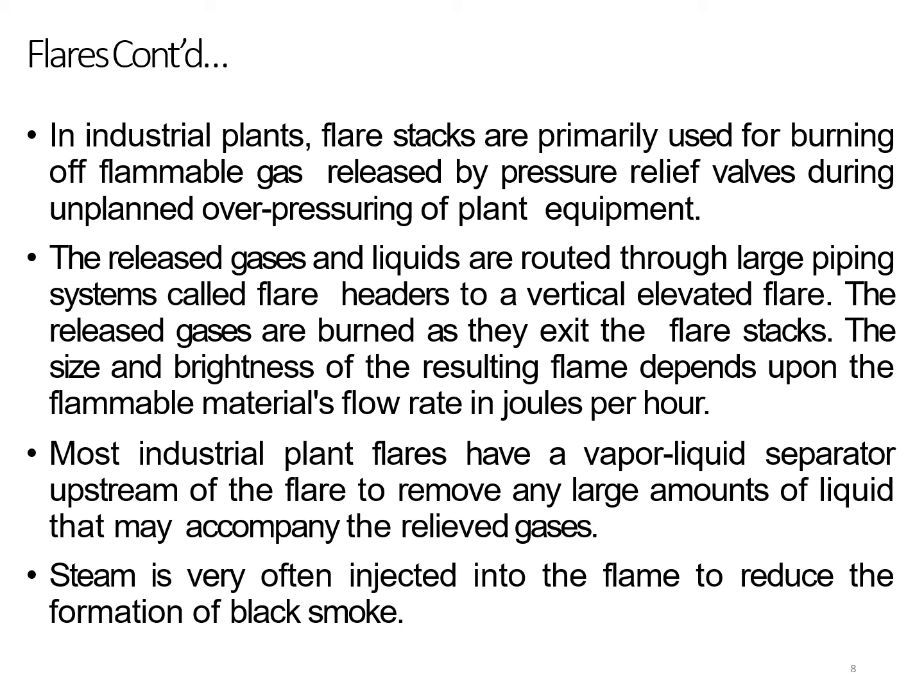The size and brightness of the resulting flame depends upon the flammable material's flow rate in joules per hour. Most industrial plant flares have a vapor liquid separator upstream of the flare to remove any large amount of liquid that may accompany the relief gases. Steam is very often injected into the flame to reduce the formation of black smoke.